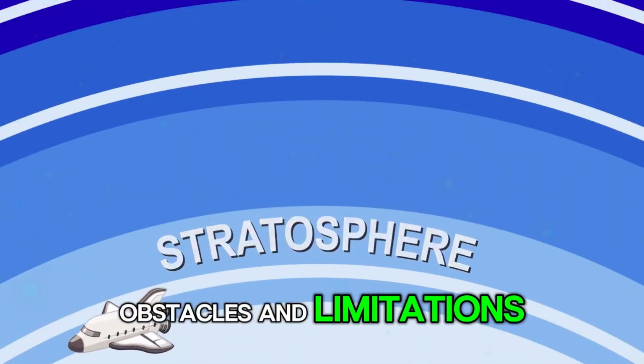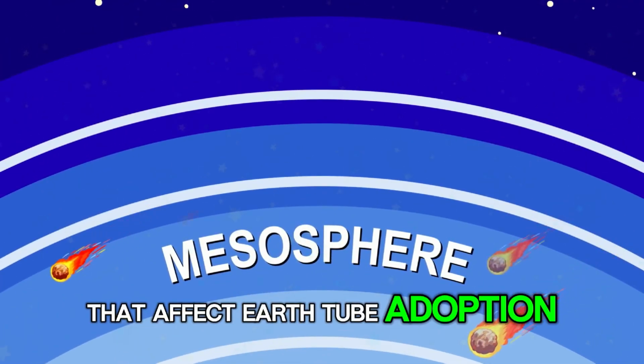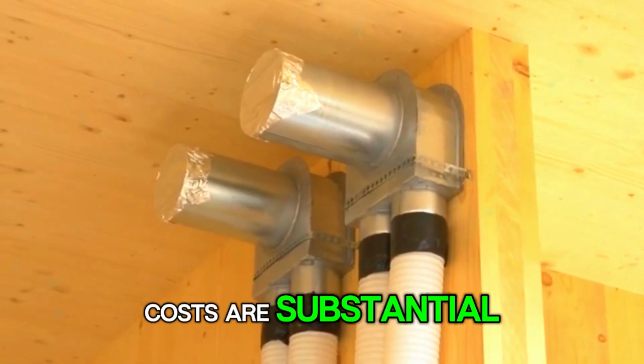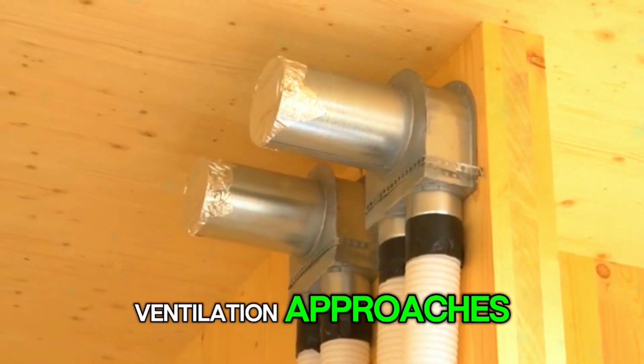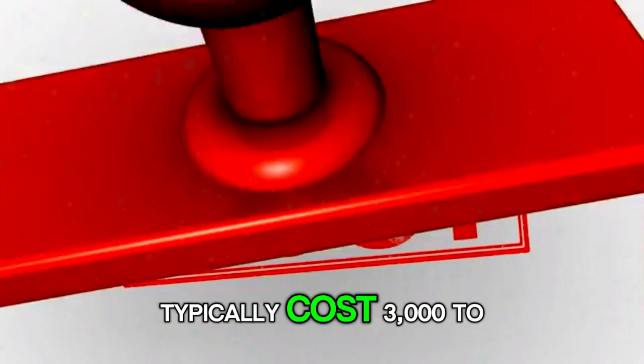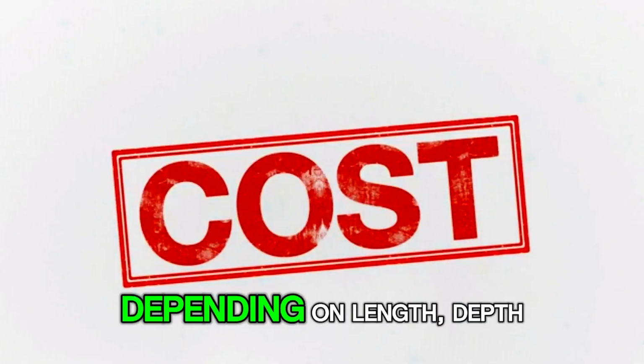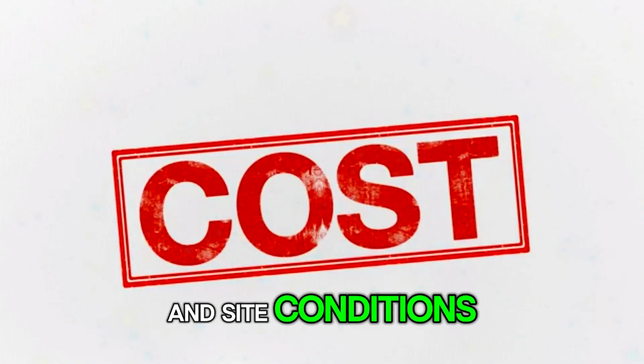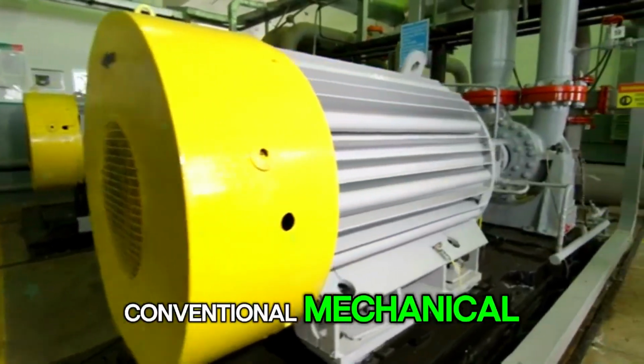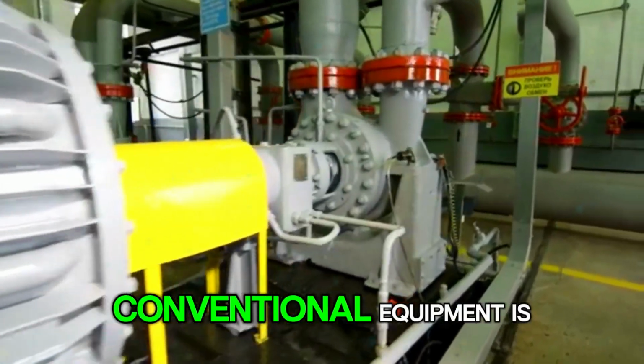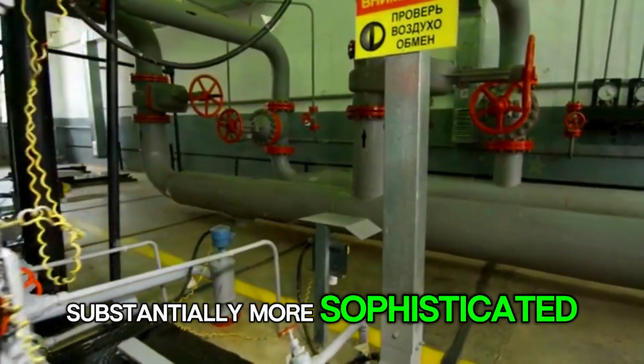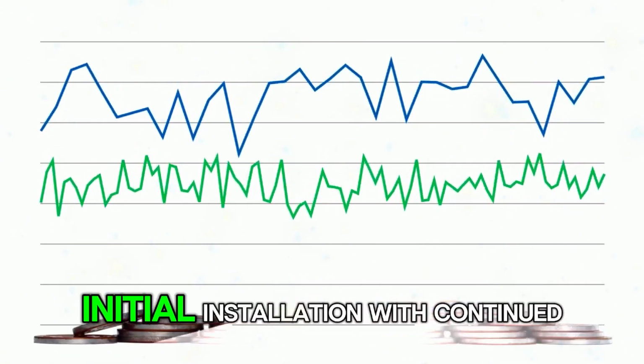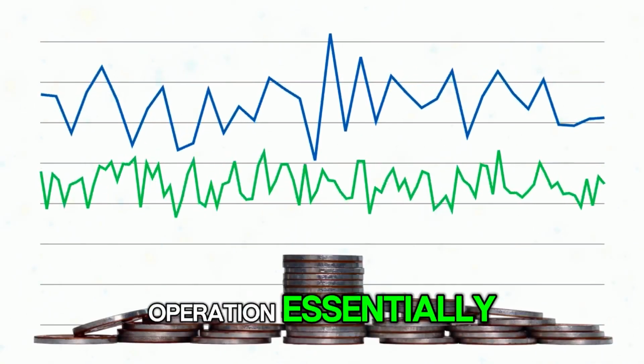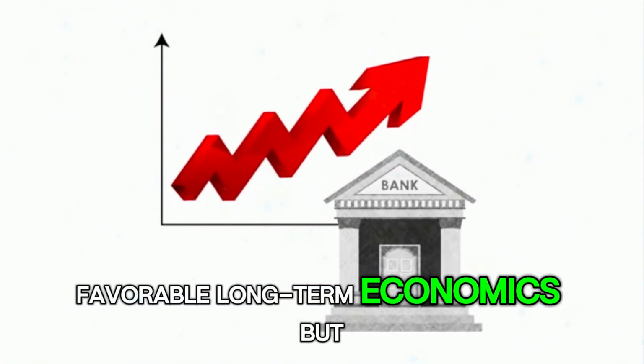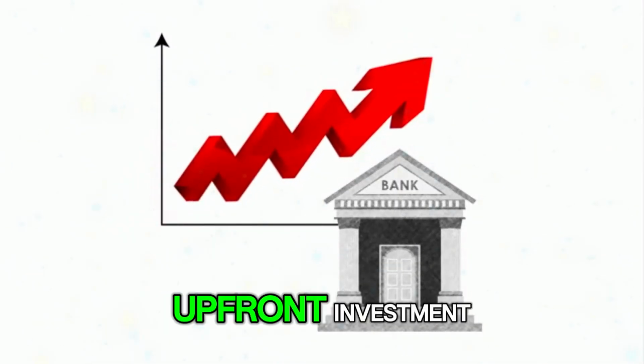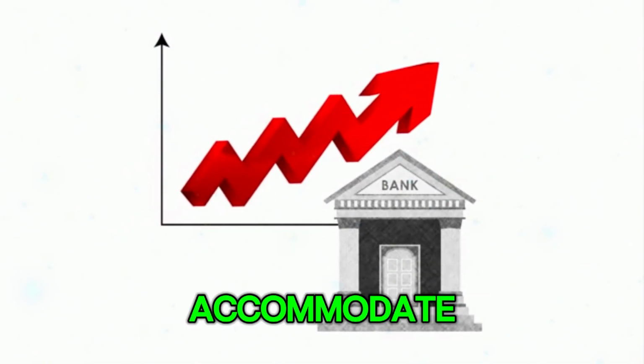Now for the obstacles and limitations that affect earth tube adoption. First, the installation costs are substantial compared to conventional ventilation approaches. Earth tube installations typically cost $3,000 to $10,000 depending on length, depth, and site conditions. The costs exceed conventional mechanical ventilation equipment, even when conventional equipment is substantially more sophisticated. The cost premium is highest during initial installation, with continued operation essentially free, producing favorable long-term economics but demanding substantial upfront investment that not all projects can accommodate.